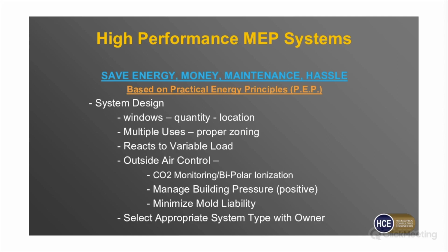There are several things to consider with outside air. One, we can control the quantity with CO2 monitoring. There are also technologies like bipolar ionization that give you the opportunity to reduce the required amount of CFM, but you still have to manage the building pressurization and maintain a net positive. We want to do all this to not only keep the environment comfortable, but to minimize the possibility of humidity issues and potential mold liability down the road.